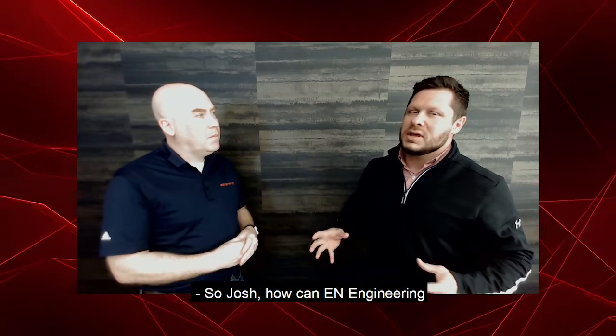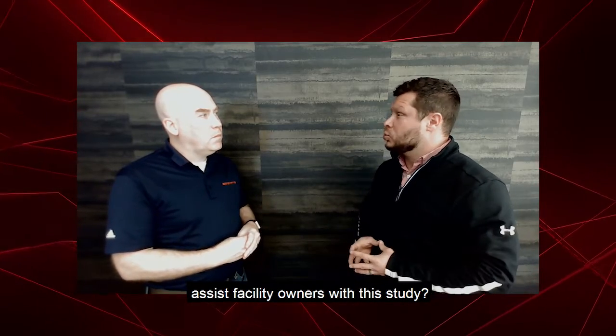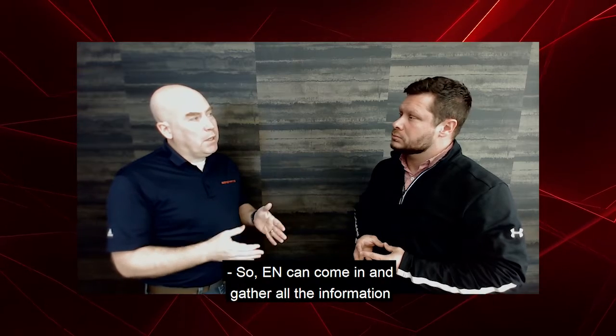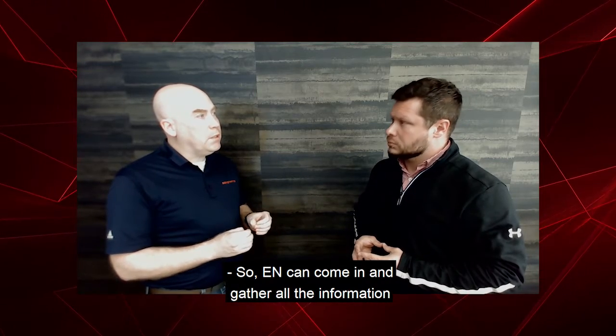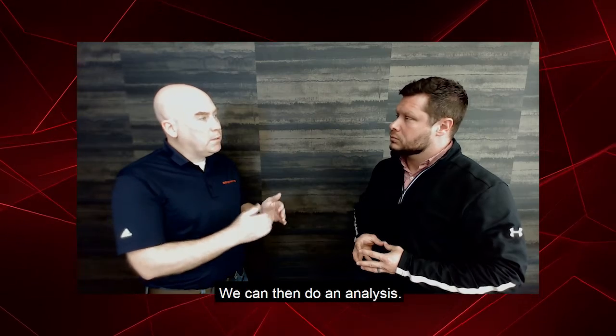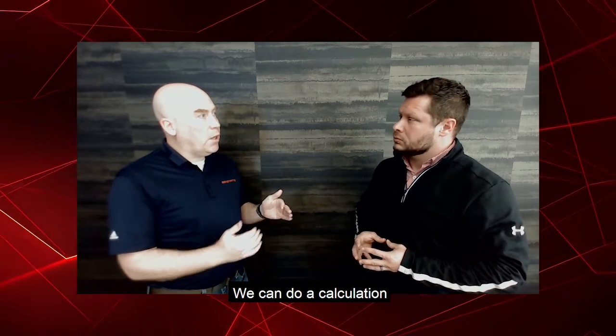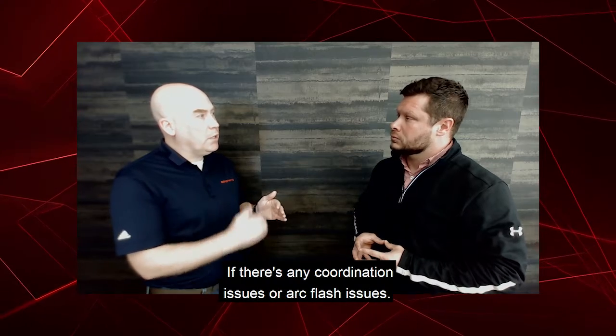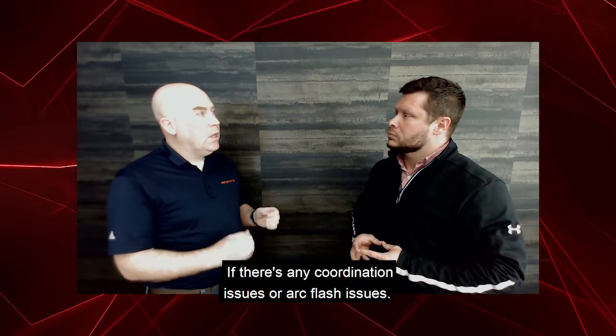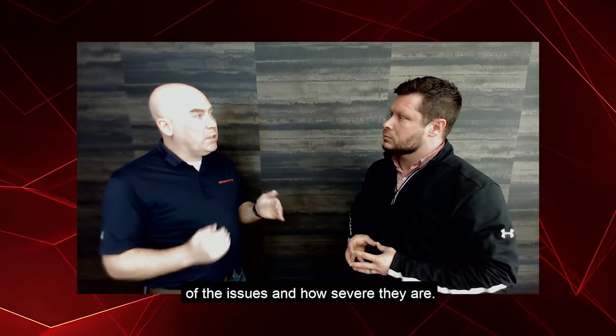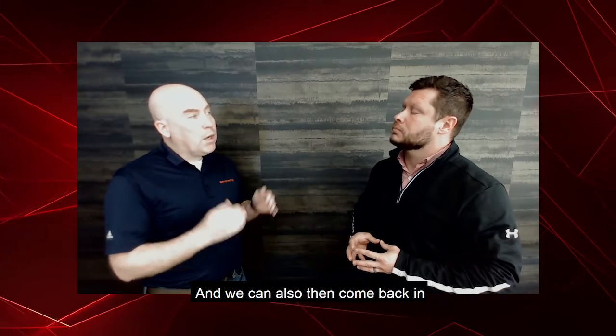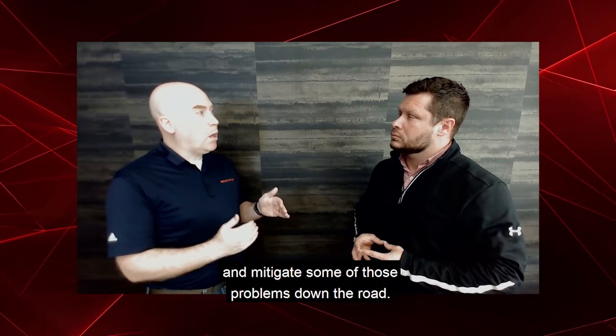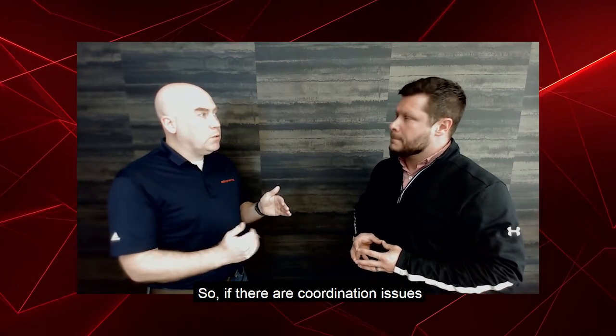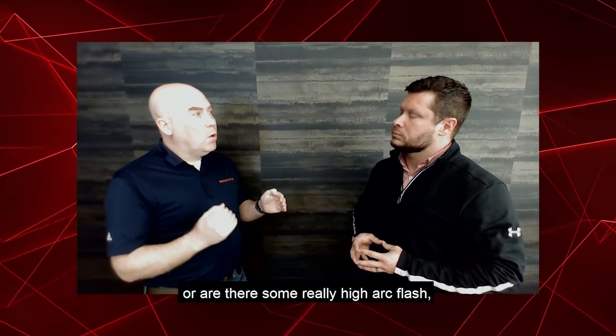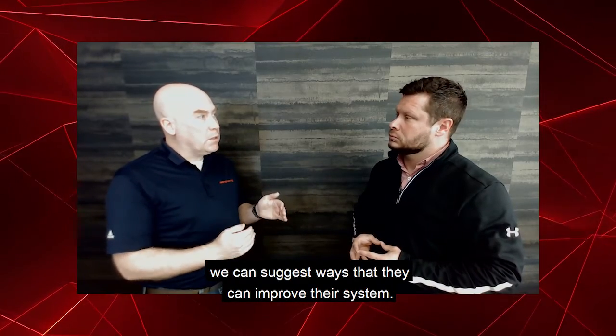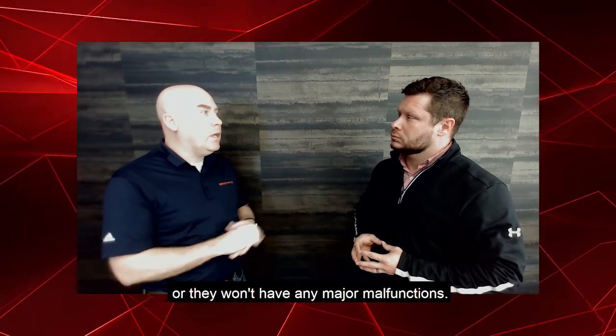So Josh, how can EN Engineering assist facility owners with this study? EN can come in and gather all the information about their electrical infrastructure. We can then do an analysis and a calculation on how well their equipment is rated, if there's any coordination issues or arc flash issues, and supply a report showing all the issues and how severe they are. We can also come back in and mitigate some of those problems down the road—if there are coordination issues or really high arc flash, we can suggest ways to improve their system so they won't have safety issues or major malfunctions.